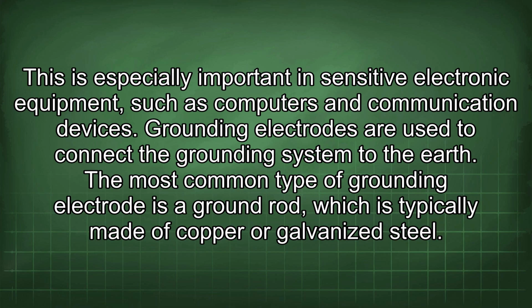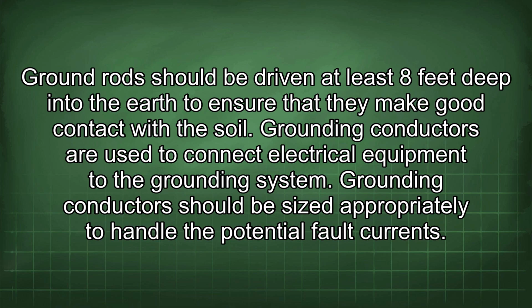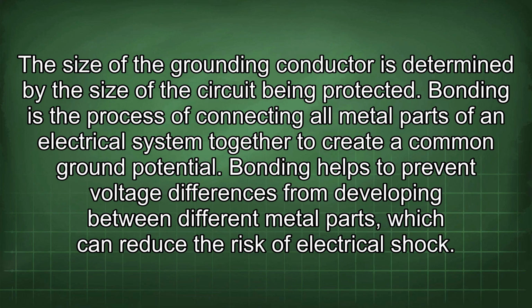Grounding electrodes are used to connect the grounding system to the earth. The most common type of grounding electrode is a ground rod, which is typically made of copper or galvanized steel. Ground rods should be driven at least 8 feet deep into the earth to ensure that they make good contact with the soil. Grounding conductors are used to connect electrical equipment to the grounding system. Grounding conductors should be sized appropriately to handle the potential fault currents. The size of the grounding conductor is determined by the size of the circuit being protected.